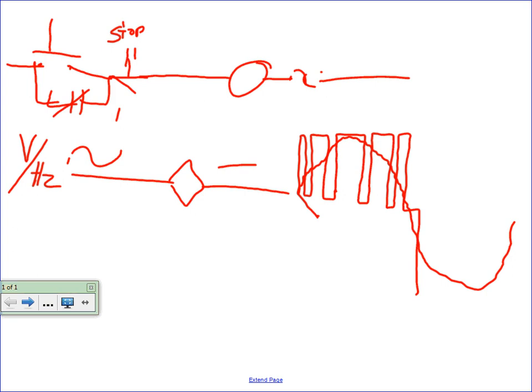And this is how all the new technology works. By varying the duration and the width of that upper pulse and lower pulse, we are changing the frequency to the motor, and at the same time we'll be reducing the amount of voltage. So now we can control the motor at any speed, and it won't burn up. And I have pictures for that too.